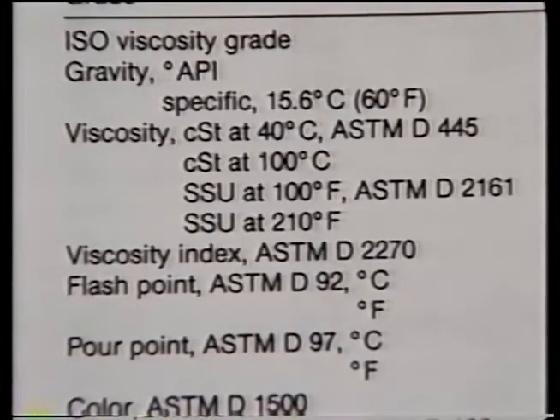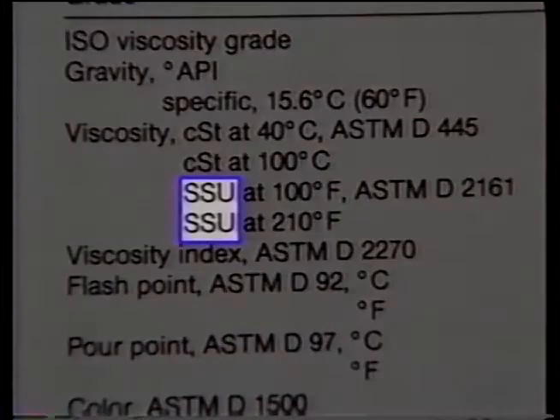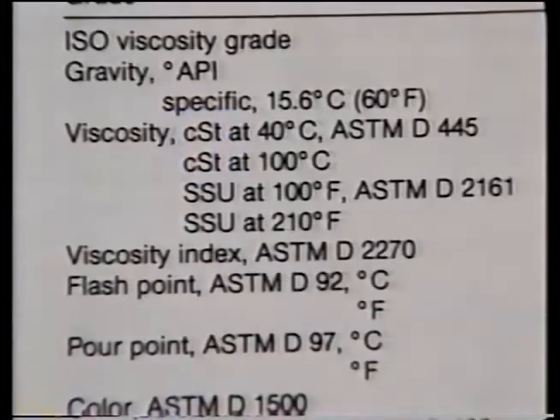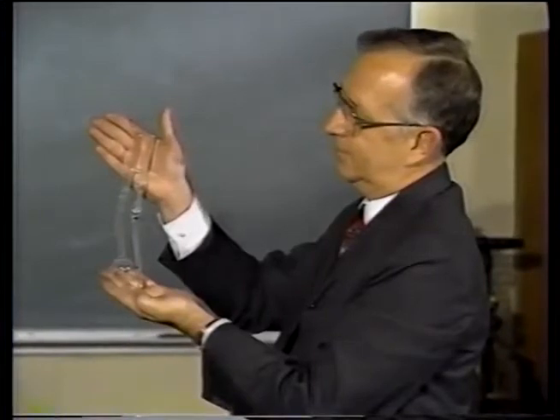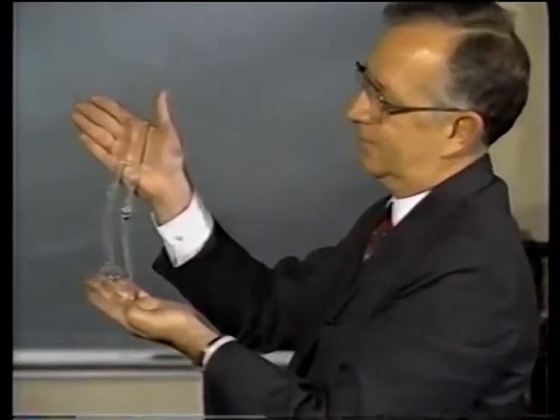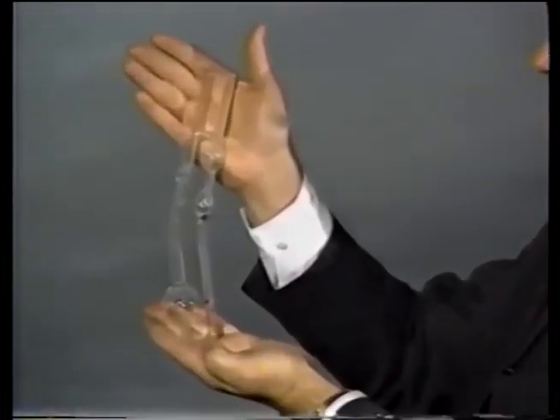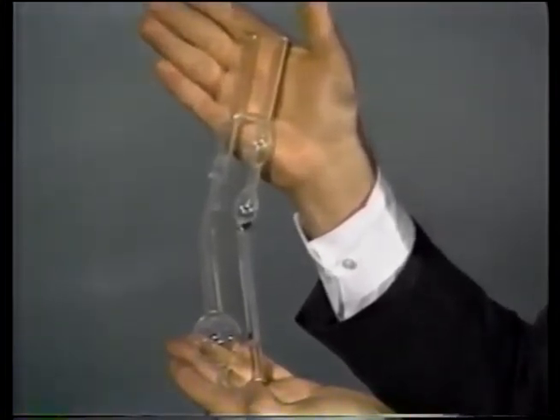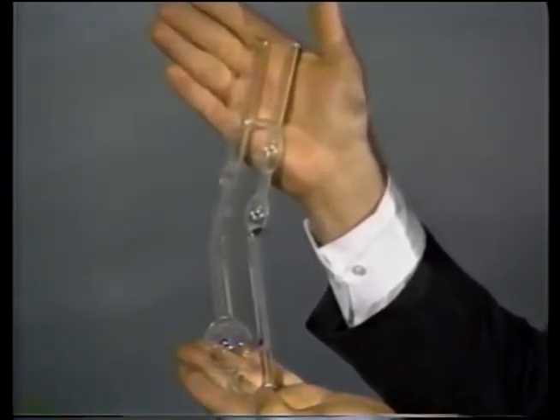Viscosity is often measured in Saybolt universal seconds, often called SUS or SSU. However, the International Standards Organization centistoke measure, CST, is becoming more common. Viscosity in Saybolt seconds is measured by a meter which times the rate at which hydraulic fluid flows through a precision-made hole at a specific temperature, usually 100 degrees Fahrenheit.